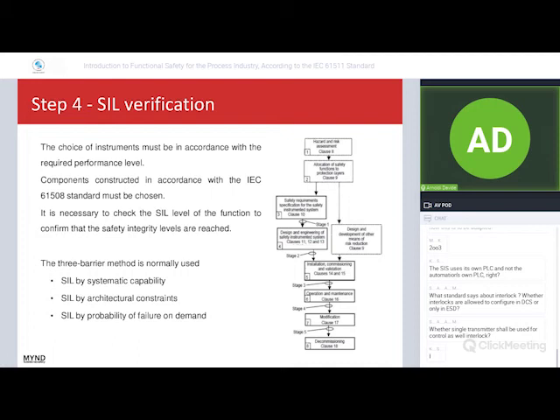So when we have described all the requirements for functional safety, we have to choose devices in the market. All devices should be according to the standard 61508. Then, using the failure rates from the vendor, the manufacturer of the devices, I can perform what is called the safety integrity level verification, using the 3-barrier method that is commonly used in the world. 3-barrier means 3 different safety integrity level checks. The first one is the systematic capability, the capability of the instruments to meet the SIL requirement.